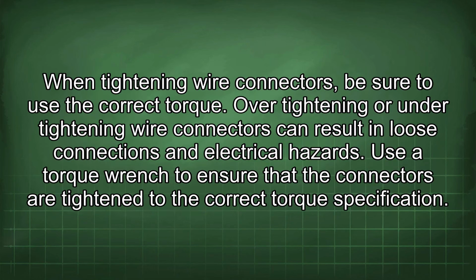When tightening wire connectors, be sure to use the correct torque. Over-tightening or under-tightening wire connectors can result in loose connections and electrical hazards. Use a torque wrench to ensure that the connectors are tightened to the correct torque specification.